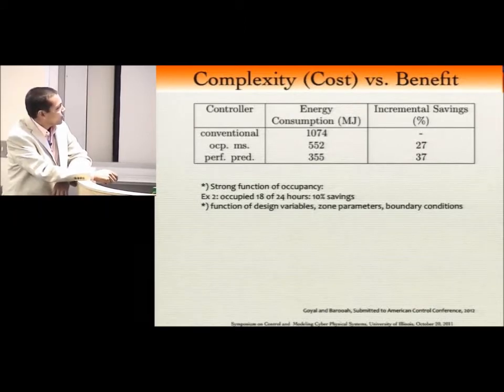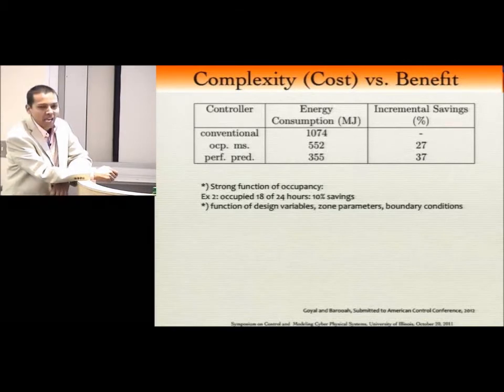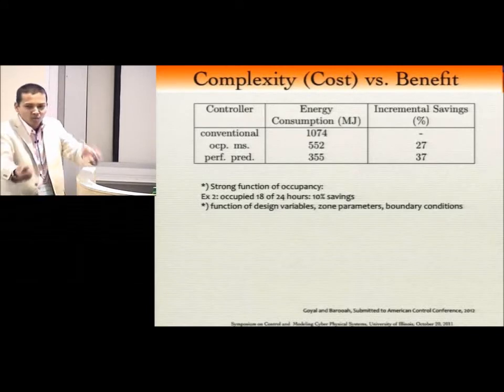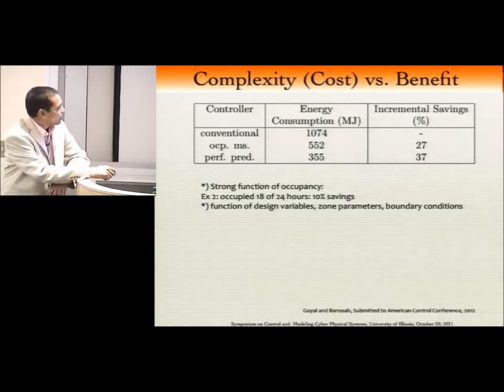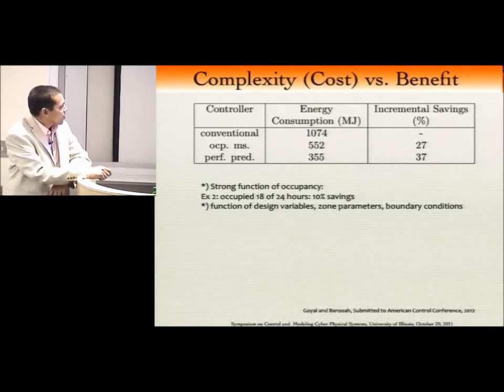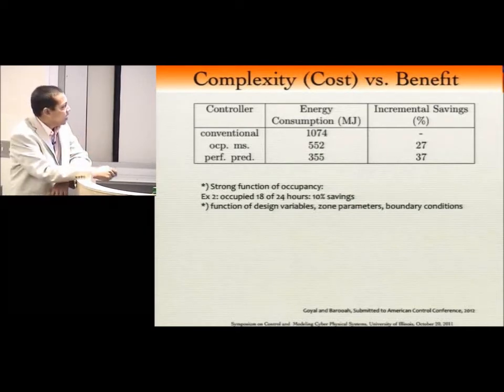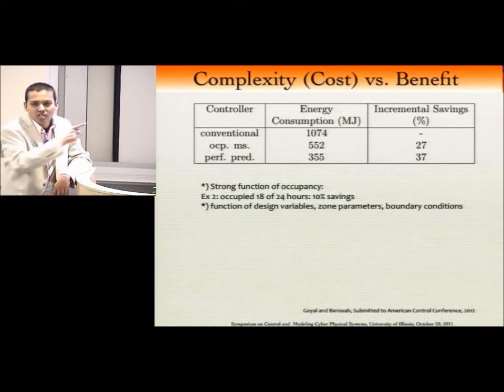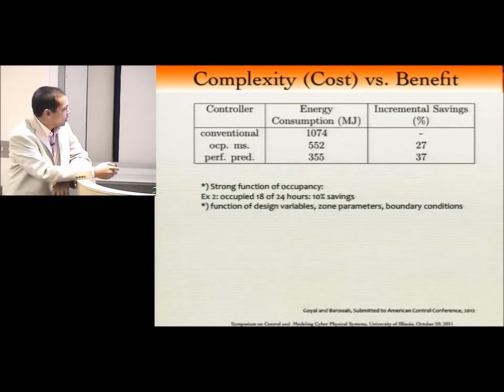Before getting too excited about these numbers, remember this is a strong function of occupancy. These numbers are for the occupancy profile I showed. If the room is occupied 18 out of 24 hours, savings are only about 10%, which makes sense since you have to keep supplying air and maintaining temperature the whole time. It's also a strong function of design variables: zone parameters, RC values, the model, and boundary conditions like temperatures in nearby zones.